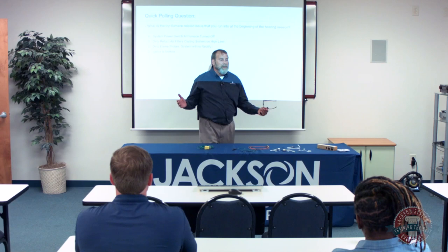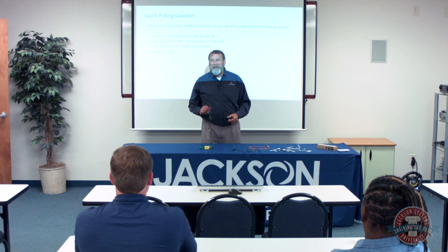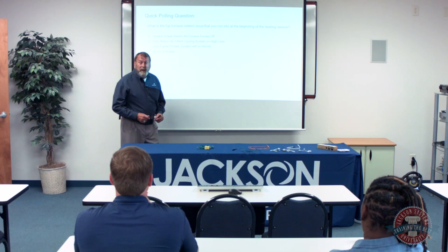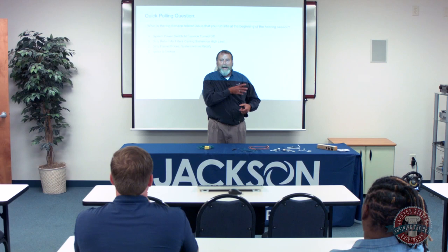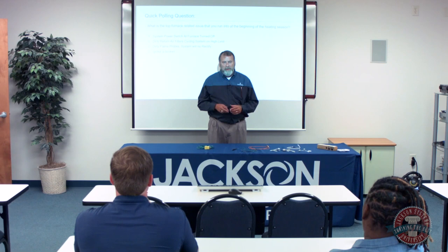Wrong. You thought it was going to be a flame rectification question to tee up for this? No. Believe it or not, it's going to be the furnace filter. You're going to run into that so many times over the next few weeks as we start going into the heating season. The furnace filter is number one. Now, here's where I'm going with this. The flame probe generally is number two.